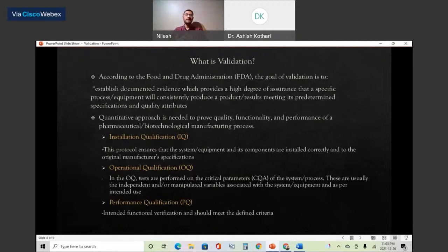But your company may have specific products, like controlled substances or anesthesia, with very tough parameters, not a broad range for acceptance criteria. If the vendor didn't do that particular test, you need to prepare a separate performance qualification protocol and do the PQ at your end, not the vendor's. So it depends on your requirements.